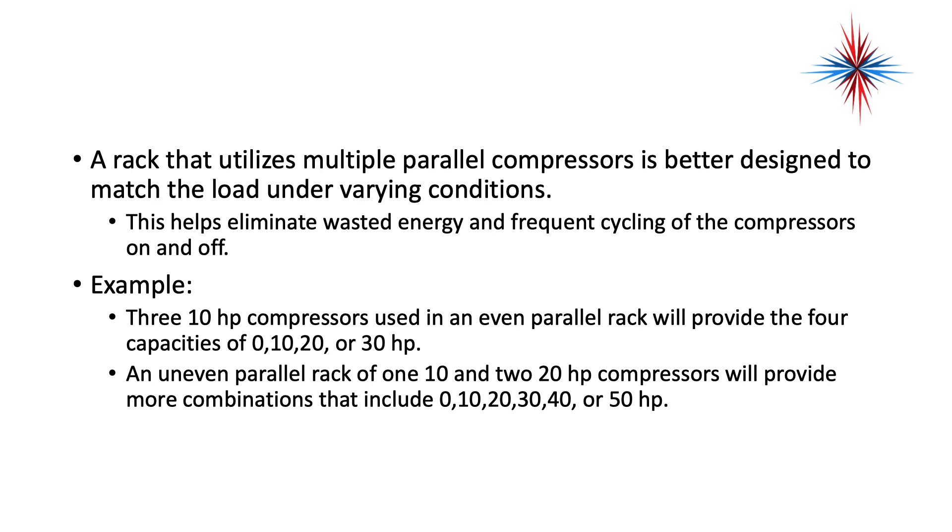Here's an example scenario. Three 10-horsepower compressors used in an even parallel rack system will provide four capacities: 0, 10, 20, or 30 horsepower. An uneven parallel rack of one 10-horsepower and two 20-horsepower compressors will provide more combinations that include 0, 10, 20, 30, 40, or 50 horsepower. So you have slightly more capacities available if you use an uneven rack system.